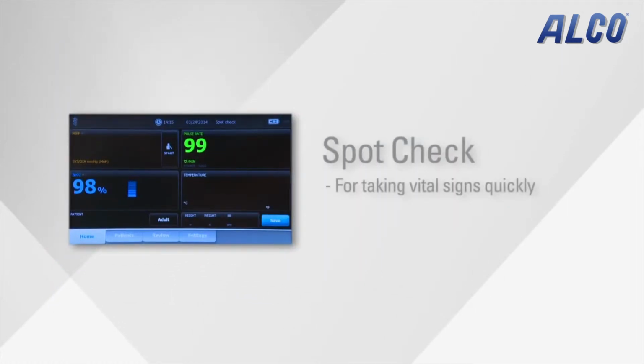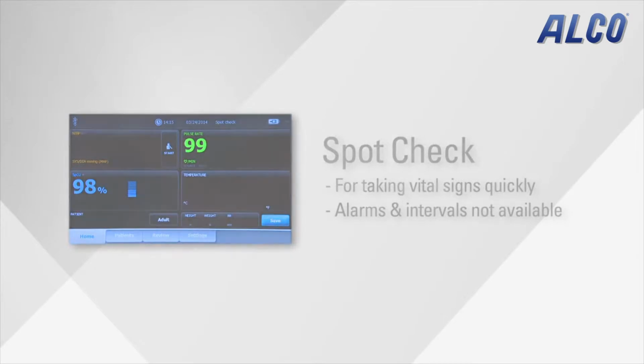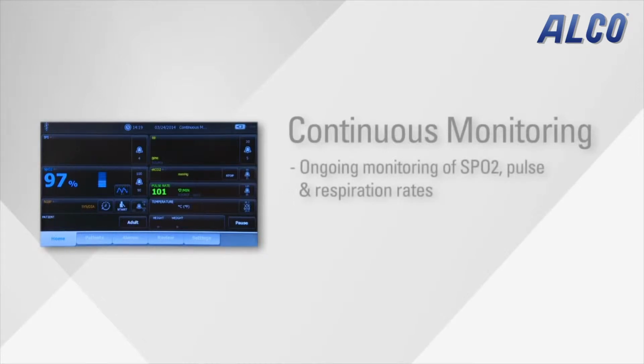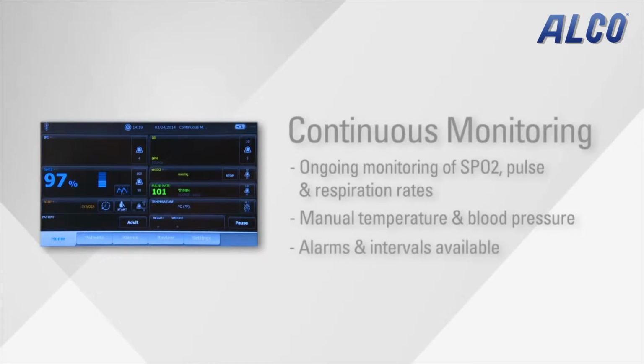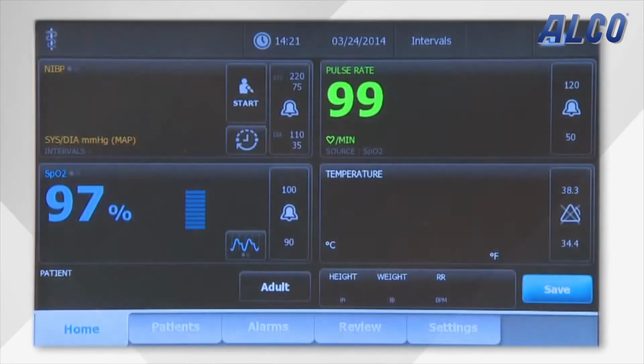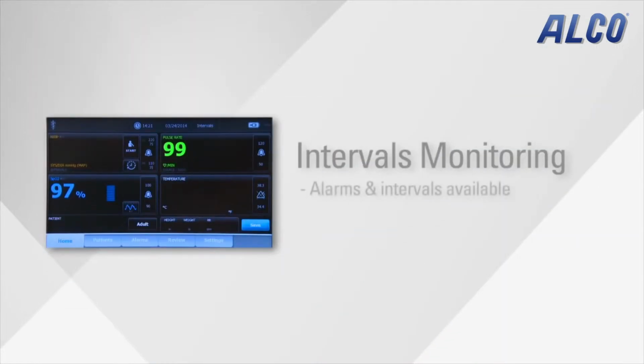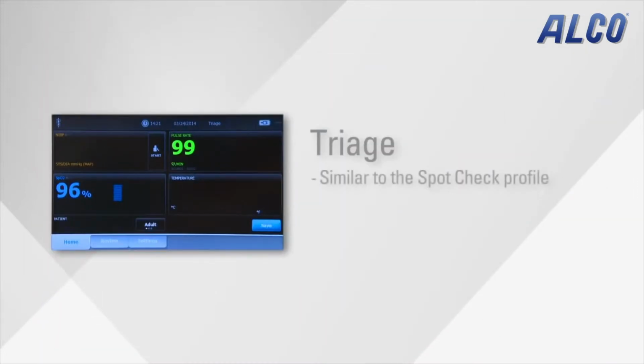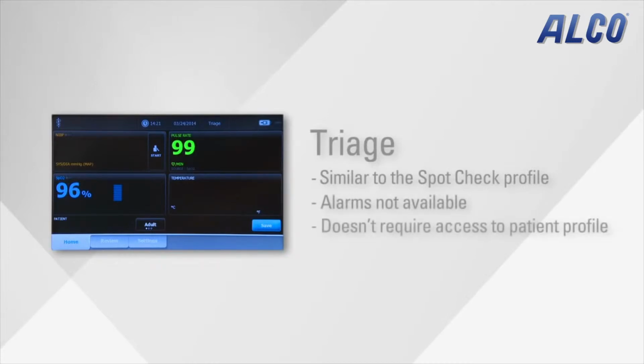The spot check profile is for taking vital signs quickly. In this profile, alarms and intervals are not available. The continuous monitoring profile allows ongoing monitoring of SpO2, pulse and respiration rates. Within this mode, you can also take manual temperature and blood pressure readings. Alarms and timed intervals are available in this mode. The intervals monitoring profile enables you to use alarms and timed intervals for taking vital signs, but does not continuously monitor. Finally, we have the triage profile. It's similar to the spot check and allows you to quickly take vital signs without alarms or access to the patient's profile.